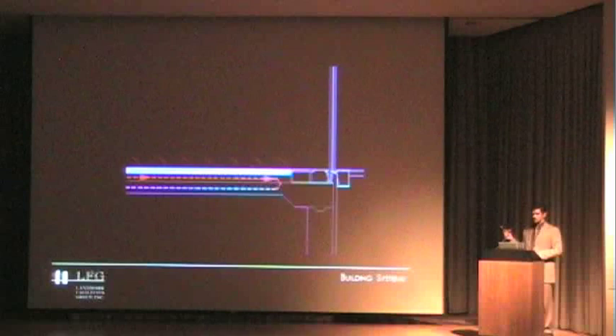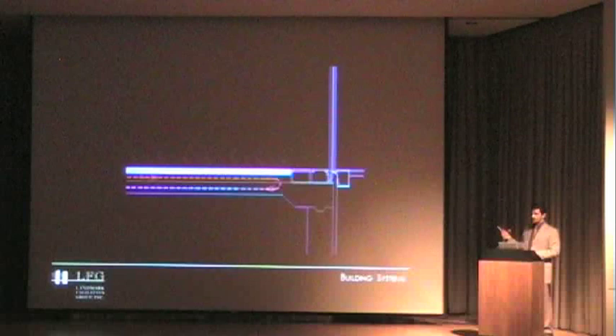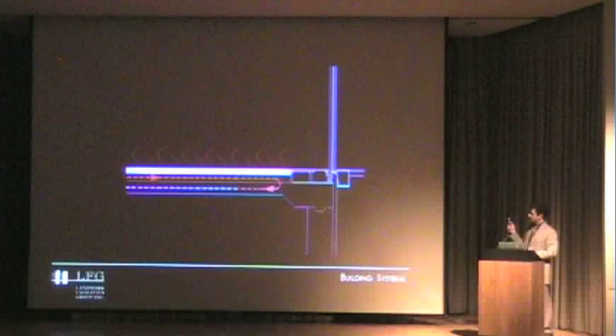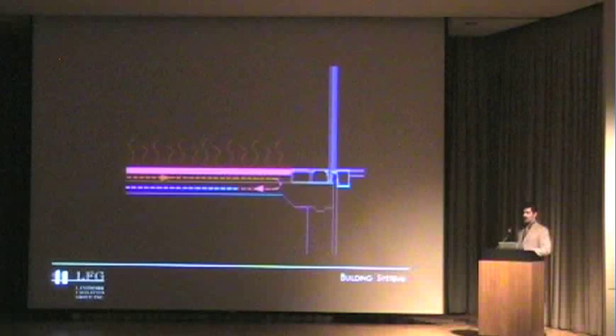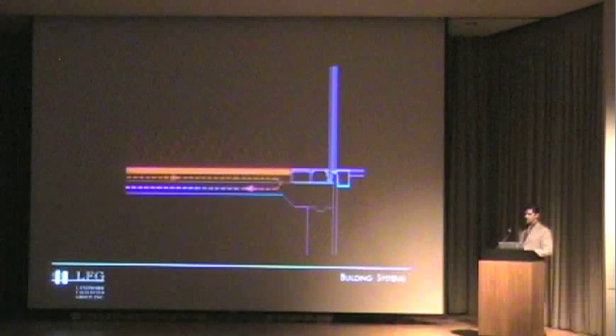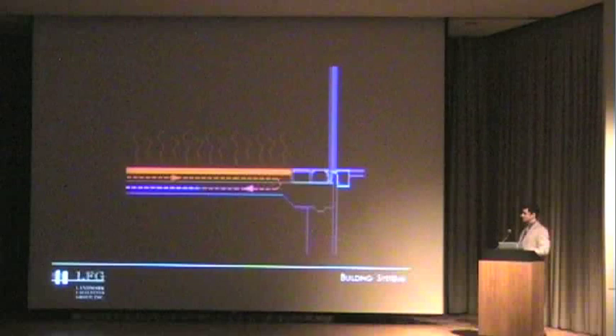I'd like to start with the radiant floor that Toshiko talked about before. In the wintertime, we have a radiant heating system installed below the slab that takes care of the primary heating load for the building. It adds to occupant comfort and helps reduce the amount of airflow we need, so that it only has to accommodate building pressurization and code-required ventilation from outdoors. By reducing that, we can reduce our fan speed a lot and increase our energy efficiency.